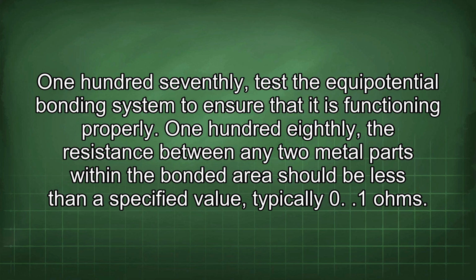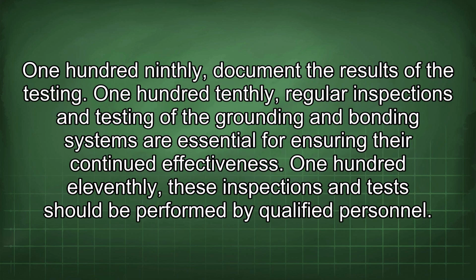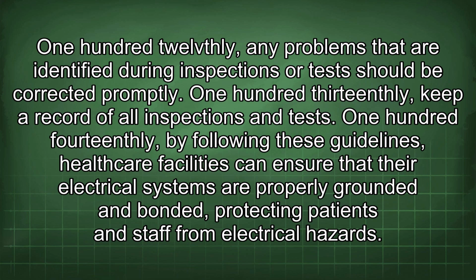107th, test the equipotential bonding system to ensure that it is functioning properly. 108th, the resistance between any two metal parts within the bonded area should be less than a specified value, typically 0.1 ohms. 109th, document the results of the testing. 110th, regular inspections and testing of the grounding and bonding systems are essential for ensuring their continued effectiveness. 111th, these inspections and tests should be performed by qualified personnel. 112th, any problems that are identified during inspections or tests should be corrected promptly. 113th, keep a record of all inspections and tests.